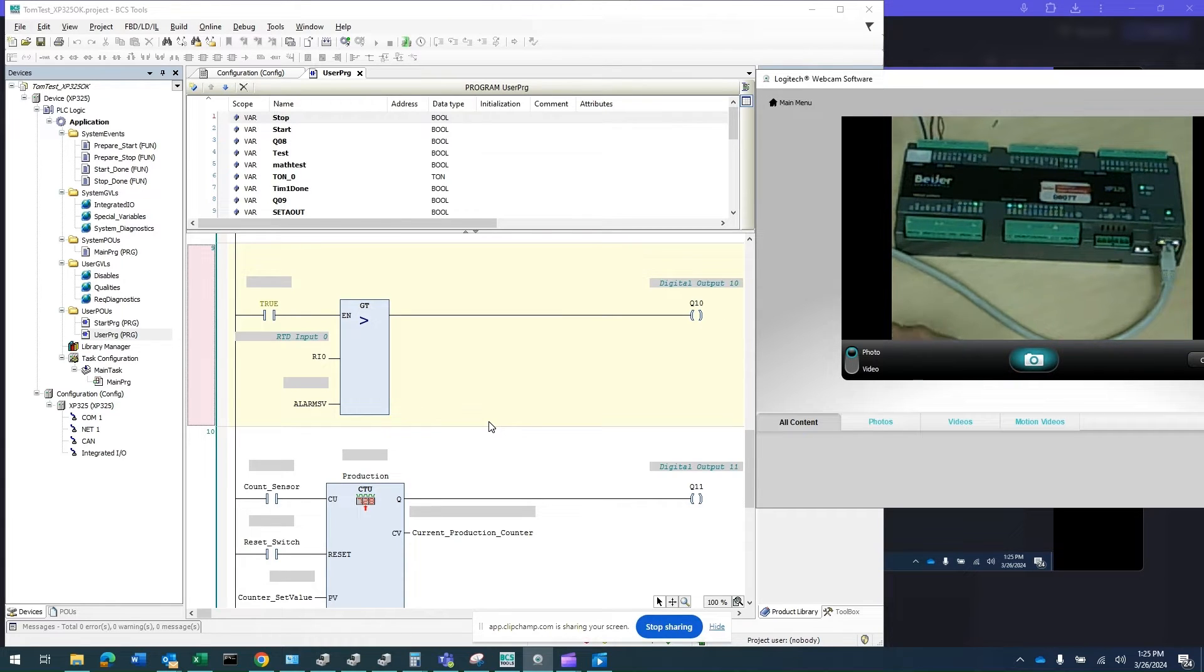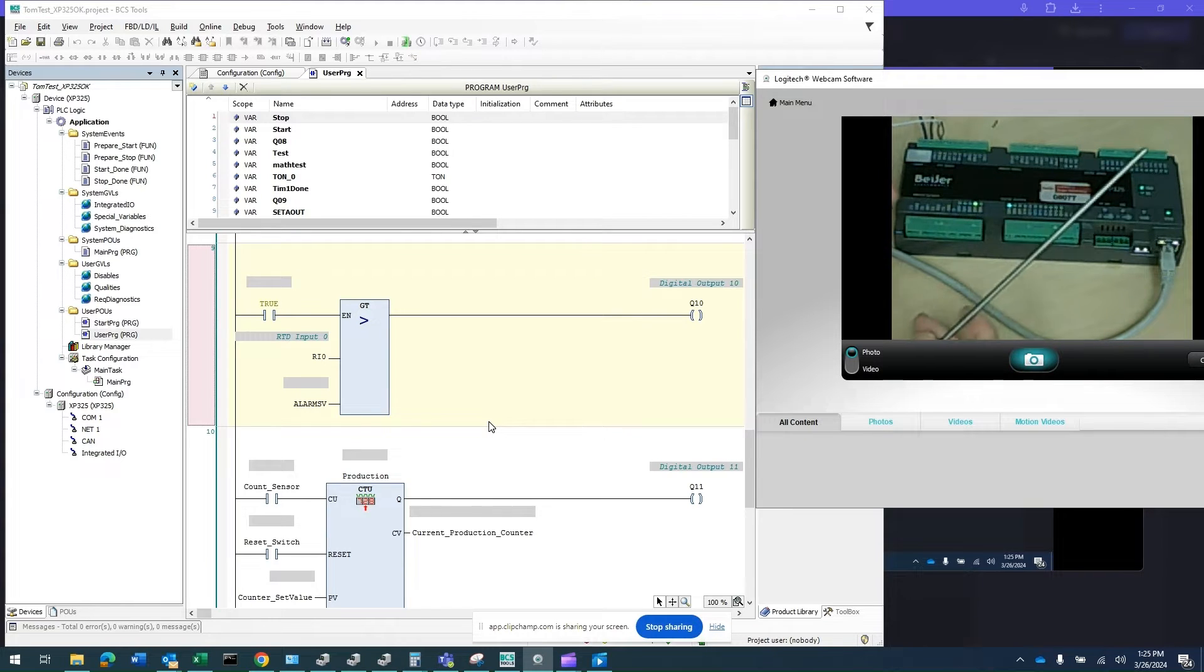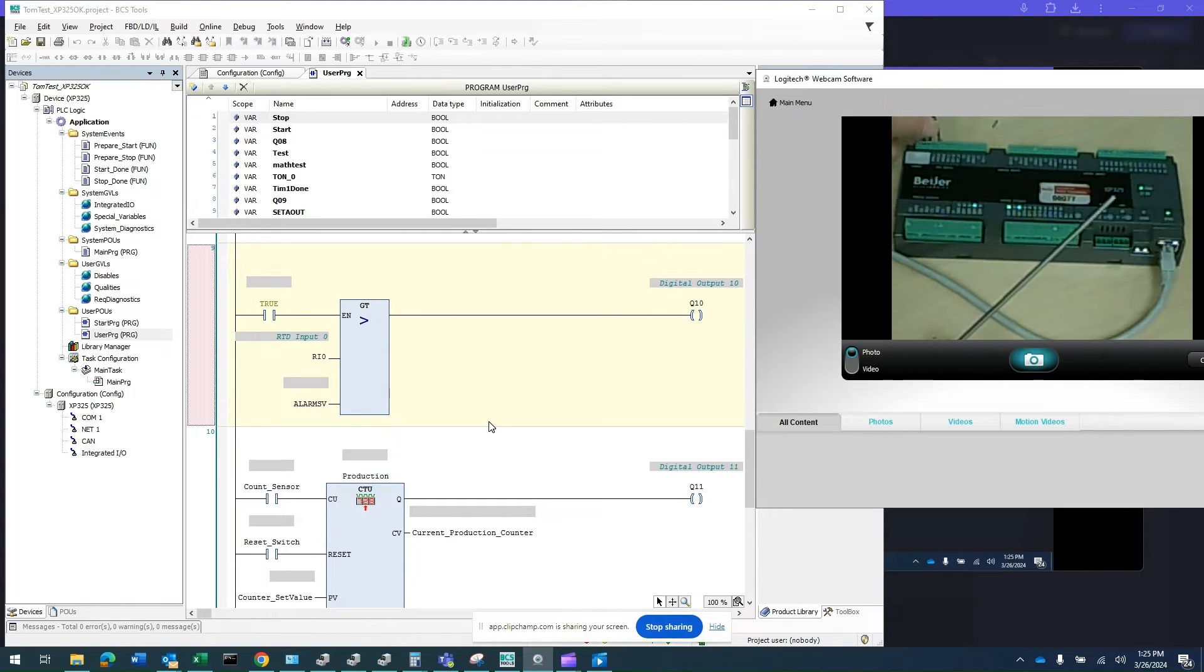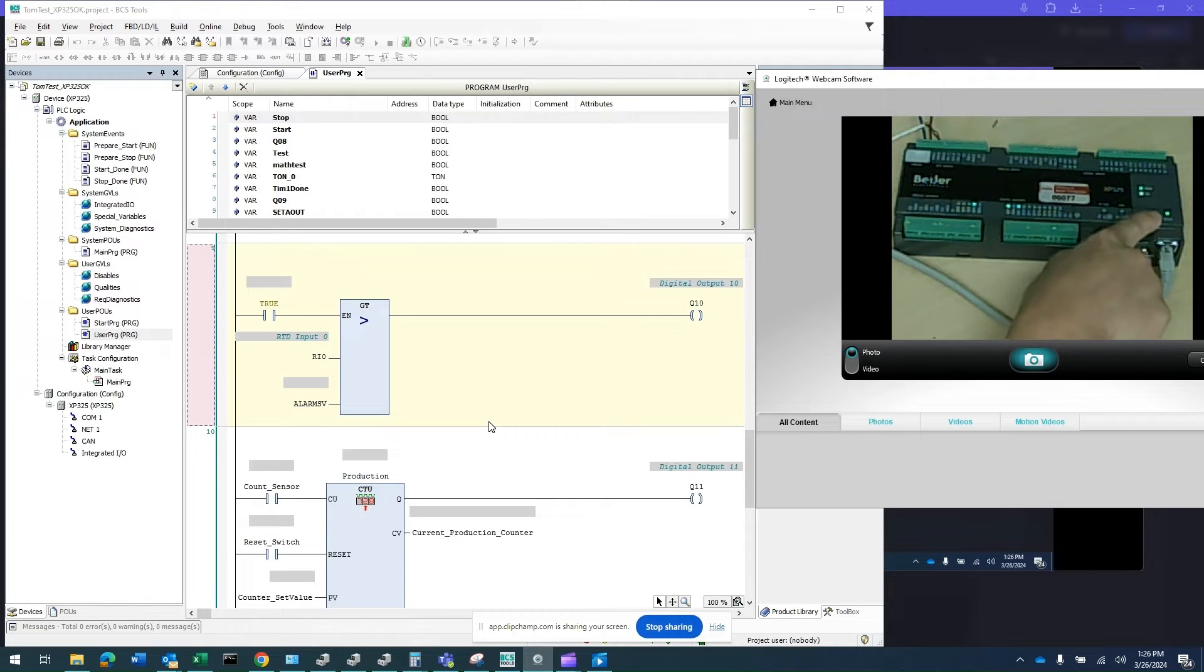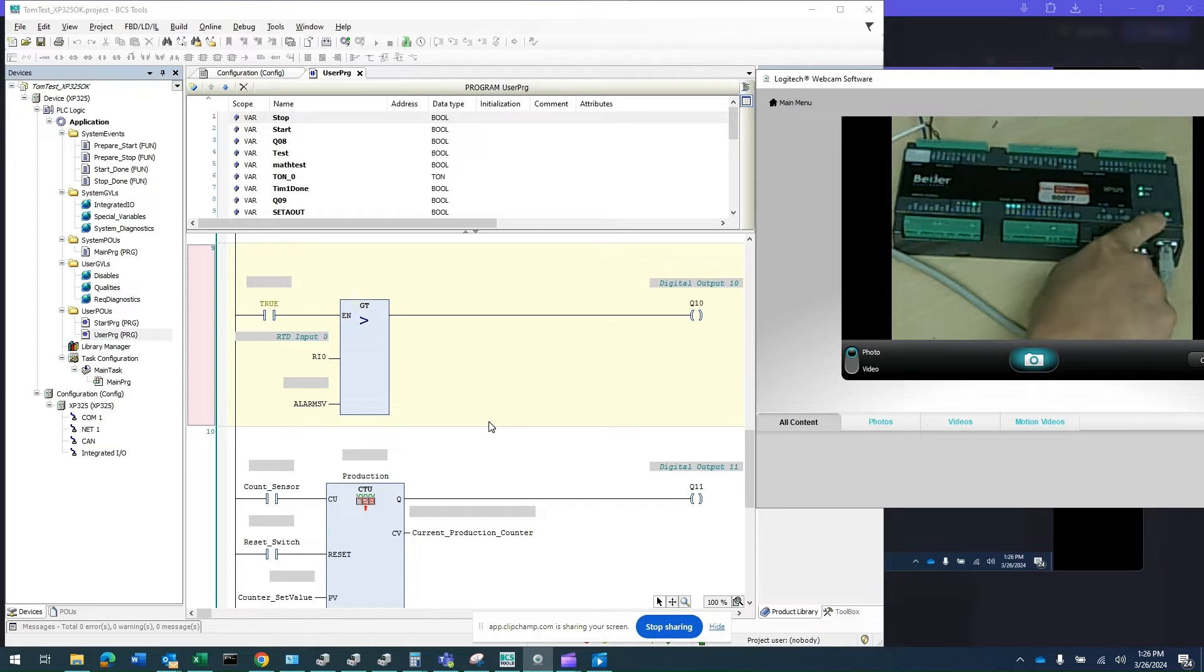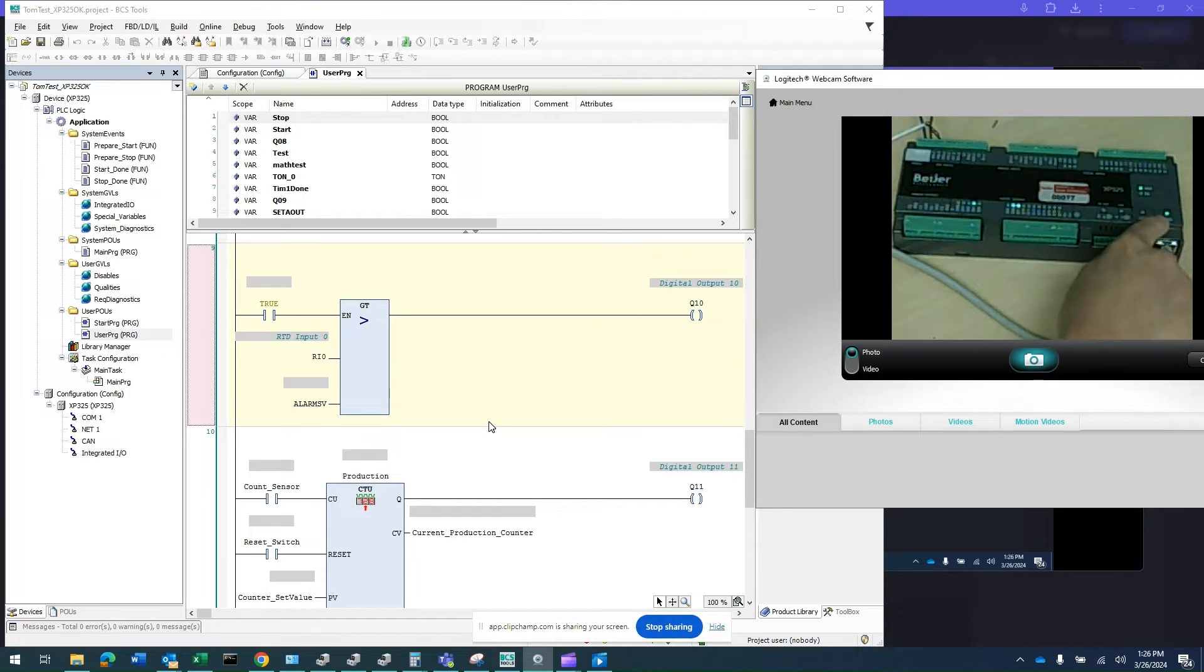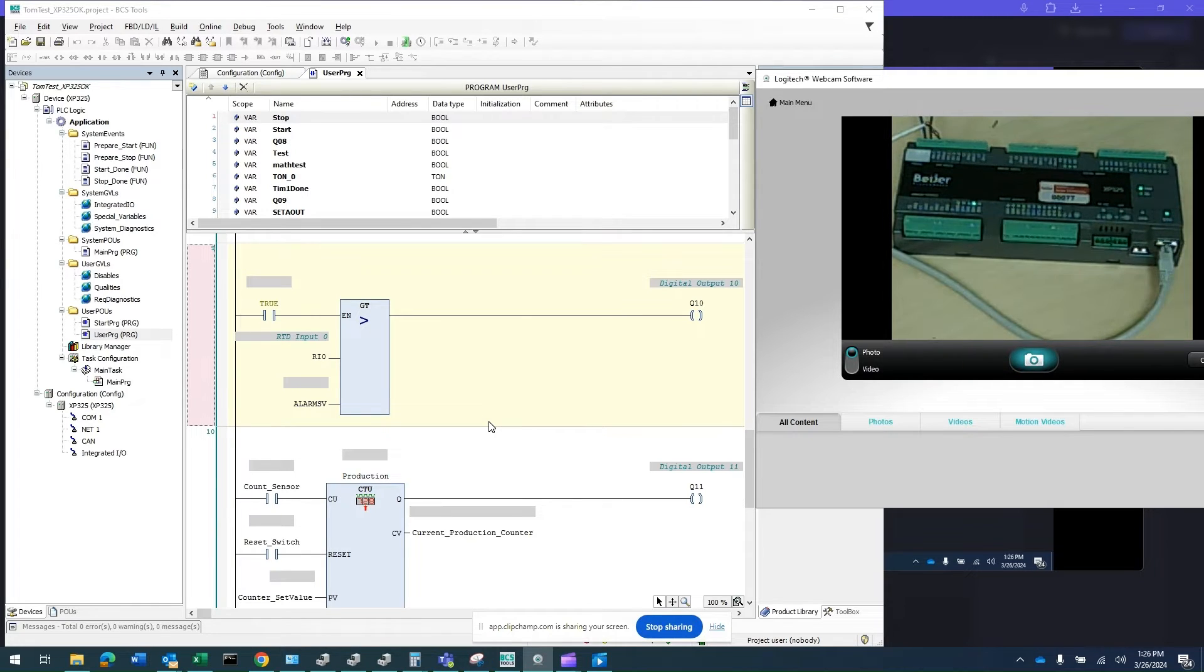I also have an RTD connected to RTD input 0, and an Ethernet cable connected to this Ethernet port. You'll notice the LED here indicates the Ethernet is solid, which means there's no communication. But as soon as I communicate to it, it will be flashing.